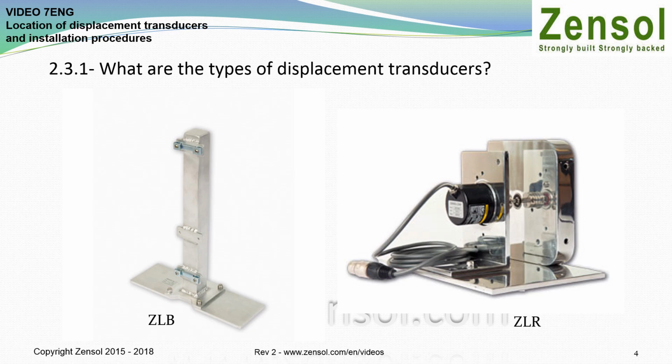To be used, these transducers must be mounted on mechanical adapters to capture and record the motion of the breaker's moving contacts. For example, the ZLR mechanical kit uses rotary transducers because it converts any linear motion into rotary motion.